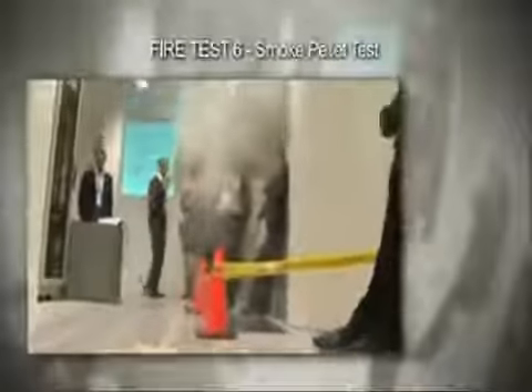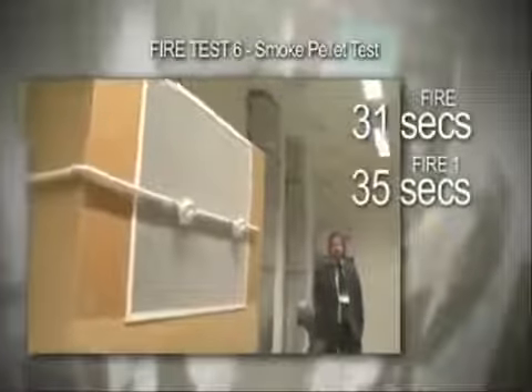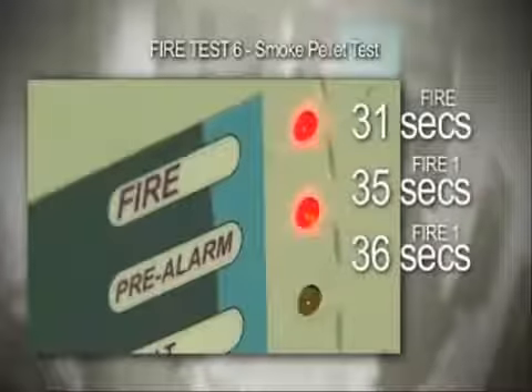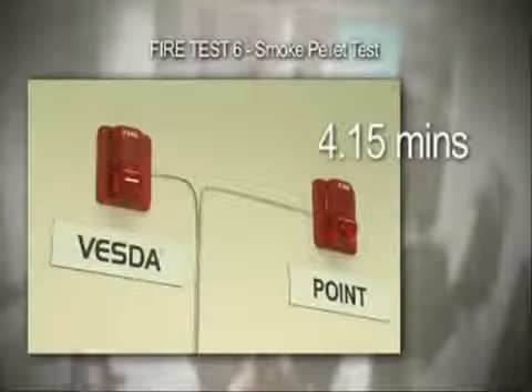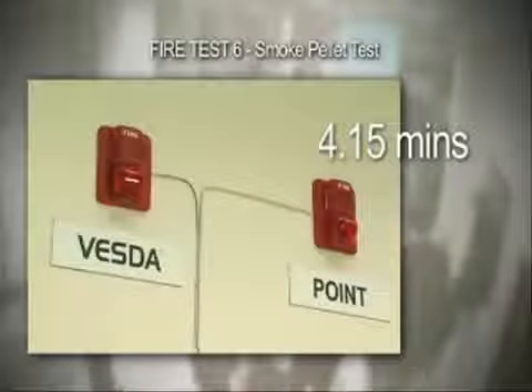This test demonstrates how much smoke is required to make the conventional point detector go into alarm. At 31 seconds, the VESDA Laser Focus cabinet detector activates fire alarm level. At 35 seconds, the VESDA Laser Compact detector across the return air grill goes into fire 1 alarm. At 36 seconds, the VESDA detector in the duct triggers fire 1 alarm. After 70 seconds, the VESDA detector on the ceiling goes into fire 1 alarm. After 4 minutes and 15 seconds, the point detector on the return air grill goes into fire alarm, which does not meet the test requirement to trigger a pre-alarm within 180 seconds. The VESDA detectors are all at fire 2 alarm at this stage.